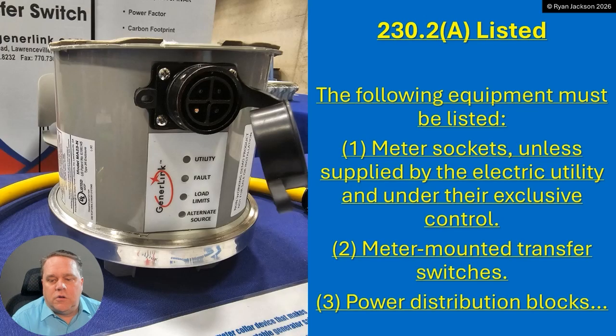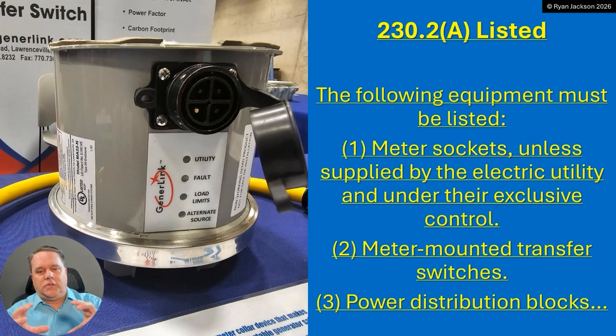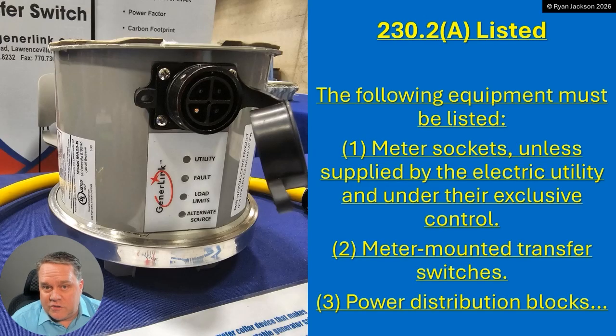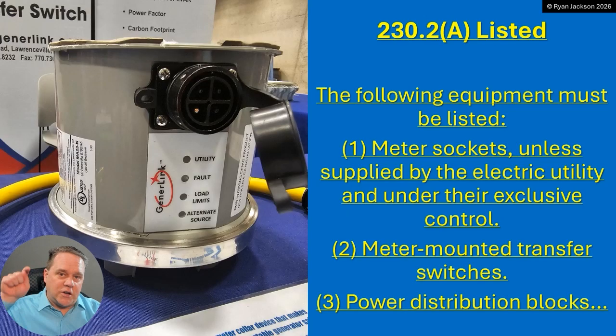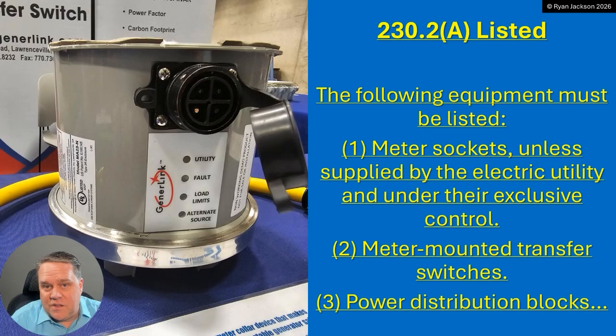Item two is a meter-mounted transfer switch — that also has to be a listed product. A meter-mounted transfer switch slips between the meter socket enclosure and the actual utility meter. You take out the meter — the utility does — you slip that thing in and then put the meter back in place, and it's a transfer switch. You can connect your generator right to it, and when it senses a loss of power from the utility, it isolates the utility, your generator kicks on, and it's unidirectional — it goes into the house but not back to the utility, so it doesn't kill any utility workers. Check with your utility before you get one of these, because a lot of utilities don't like it, and if they say you can't use it, you can't use it.